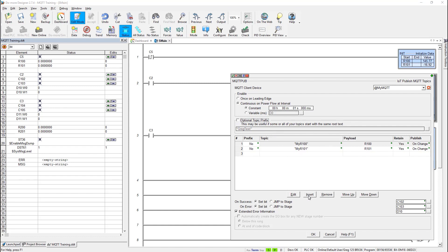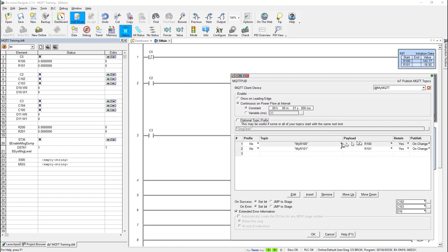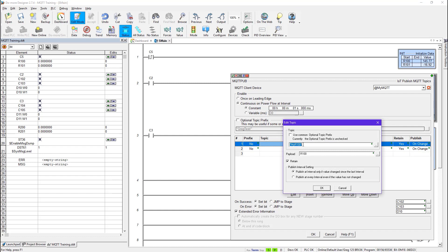So normally I would use the insert button to put in a new topic. But here I put in two topics. I've called one my r100 and my r101. And it's pointing to these elements in the memory of the Bricks PLC. You also see that these are set to retain. And here's the other thing to publish is to publish this value on change. So what this means is in the way I have this set up, every second it's going to go down through here and see has r100 its value changed since the last second that I looked at it. If it has changed, then publish it. If it has not changed, then don't publish it. Don't waste time out on the wire, in other words, if it hasn't changed. There's no need to republish the value.